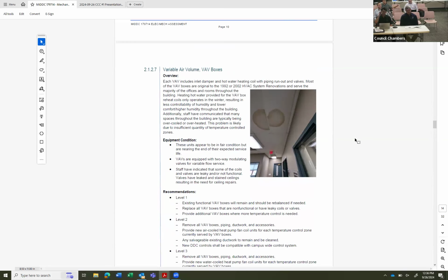Moving on to the variable air volume boxes. There are currently VAV boxes with hot water reheat coils serving all the zones in the building. The one part about this system I wanted to mention is that it does only run in the winter, so we are limited in how much level of comfort we can provide, because when we allow the variable air volume reheat portion to run in the summer, we can reheat the air to prevent overcooling in spaces.